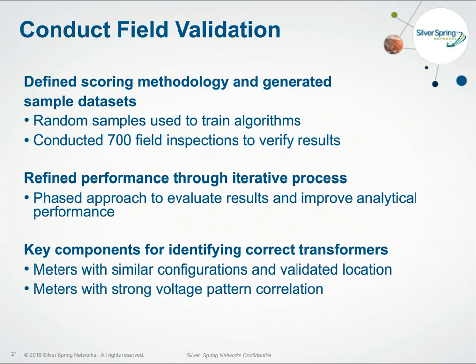The key to success of any analytics project is a strong partnership with the customer. Over six phases and 700 field inspections, we refined the models significantly. We found things you wouldn't think of in the office but discovered in the field — for example, all other meters on a transformer sharing the same address inside a street. A lot of field insights got built into the suggestions over time. Probably the biggest finding was that voltage correlation turned out to be incredibly powerful.